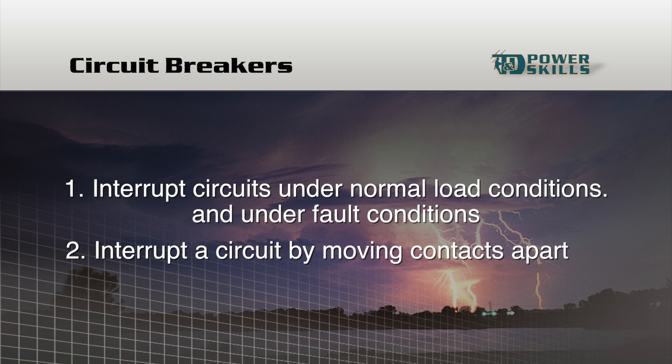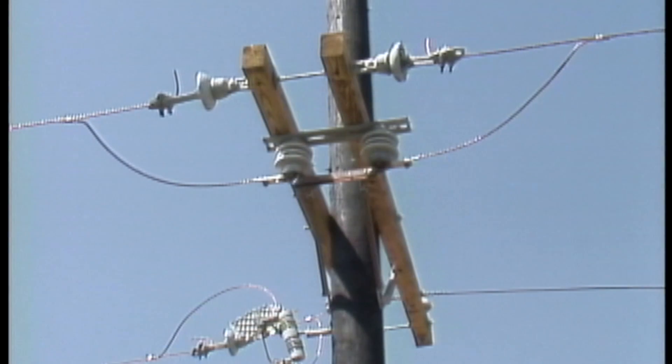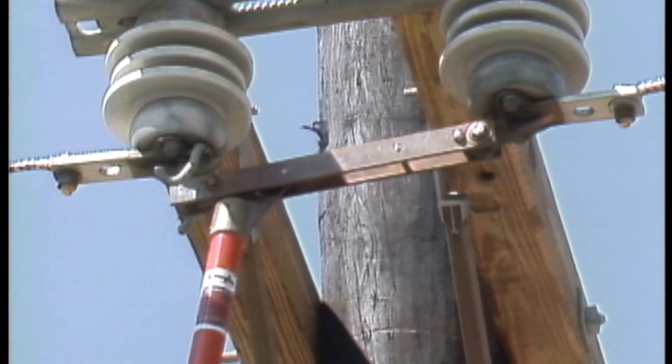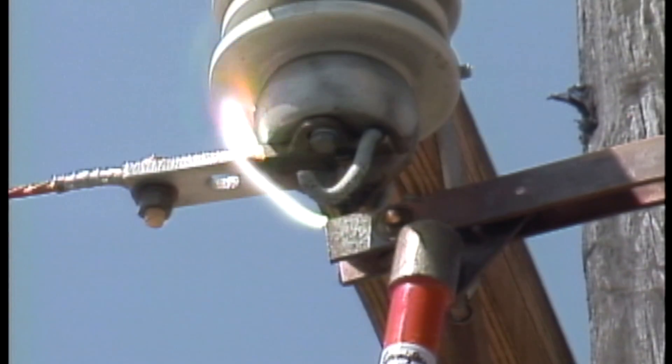A controlled arcing demonstration using a disconnect will help to show why. In this demonstration, a closed disconnect establishes or makes an energized circuit. When the disconnect switch is opened, current tries to bridge the gap in an attempt to maintain the circuit. The air heats up and becomes a conductor. As a result, an arc forms.